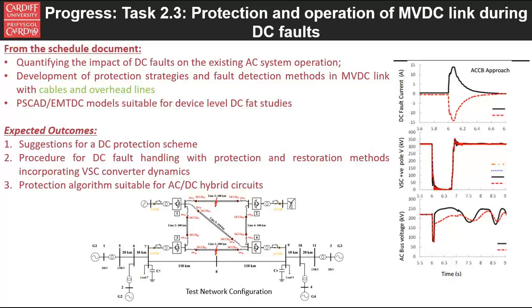And also, if this DC technology will be used in different locations and other systems in the UK, or even used for DC overhead lines, how do the converters deal with this transient fault, and how do we identify and restore the system, and also consider this combination? This is a quite interesting point of this particular project, the combination of the cable and the overhead line. Because we have already done some HVDC protection, we will use some of the knowledge and apply it to the medium voltage level, and then investigate this DC protection response, fault response, and operation.